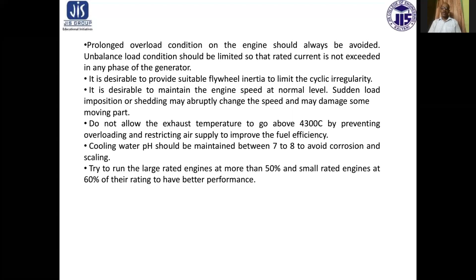Do not allow the exhaust temperature to go above 430 degrees centigrade, by preventing overloading and restriction of air supply, to improve the fuel efficiency. Cooling water pH should be maintained between 7 to 8 to avoid corrosion and scaling. And the last point, try to run the large rated engines at more than 50% and small rated engines at 60% of their ratings to have better performance.